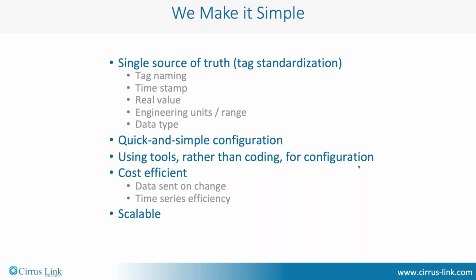We talked in the previous webinar about getting data effectively from the field into an Ignition gateway. But cost efficiency also comes into play when connecting to the cloud, because every time we publish a piece of information, it is just micro cents. But if you're doing that for millions and millions of tags, you need to be very efficient and only send data when it changes. If you have a value that is 12, you don't need to publish it every 1 second to know that, because with MQTT we have state, so you know the value at any point in time.